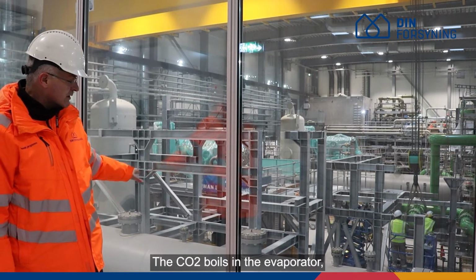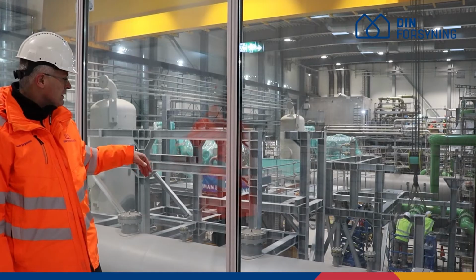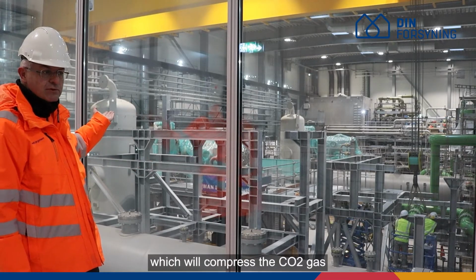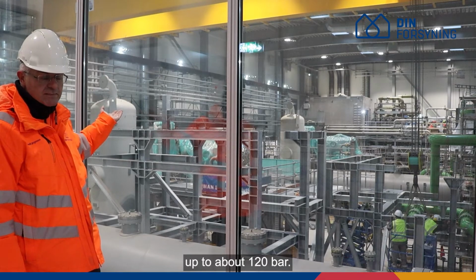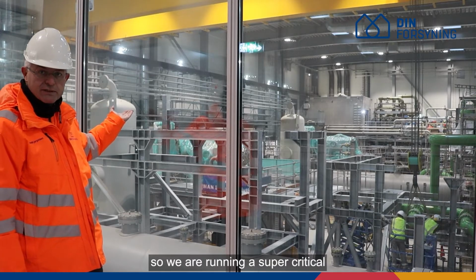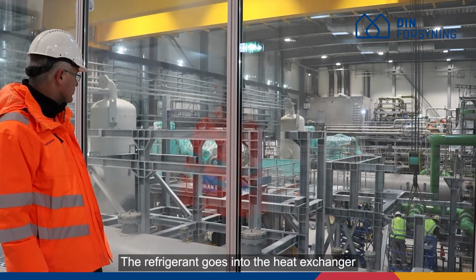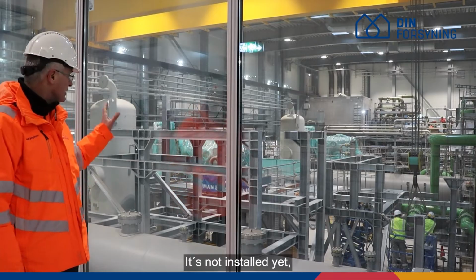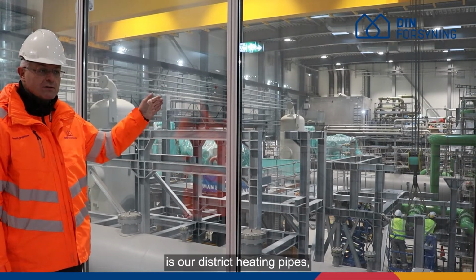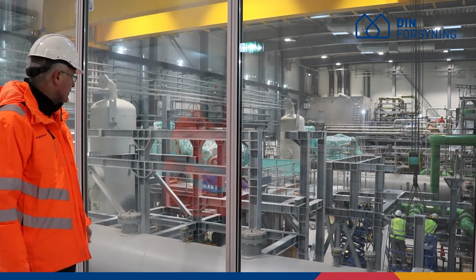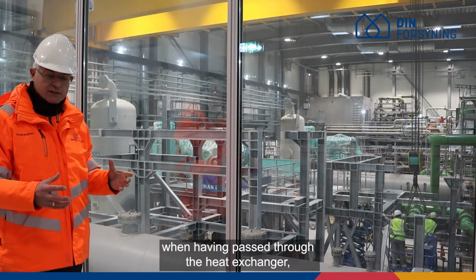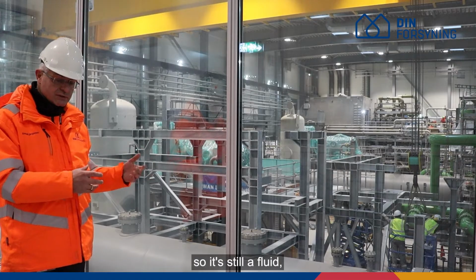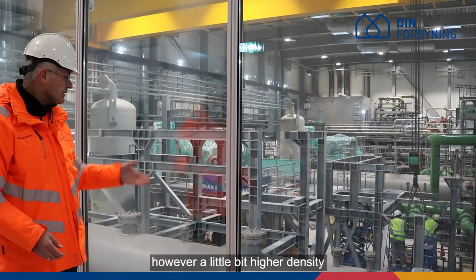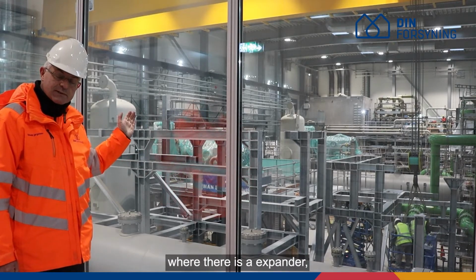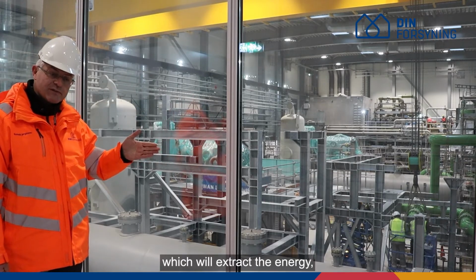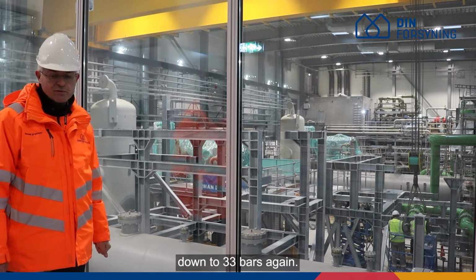The CO2 boils in the evaporator at a pressure of about 30, 35 bar. It's taken to the compressor, which you can see behind us, and which will compress the CO2 gas up to about 120 bar. That is above the critical point, so we are running a supercritical refrigerant cycle here. The refrigerant goes into the heat exchanger for the district heating system. It is not installed yet, but what is installed is our district heating pipes, which are on the wall here. And from there, having passed through the heat exchanger, the CO2, which is still supercritical, so it's still a fluid, however with a little bit higher density, will go back to the other end of the compressor where there's an expander, a small turbine, which will extract the energy which is in the pressure down to 33 bars again.